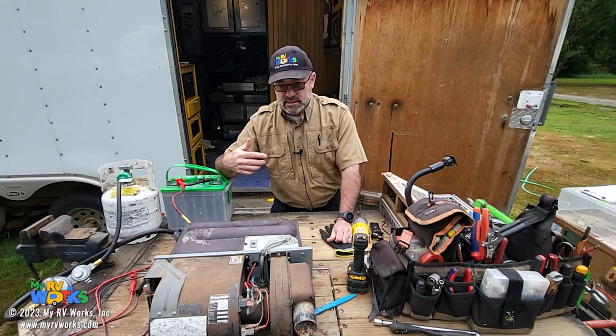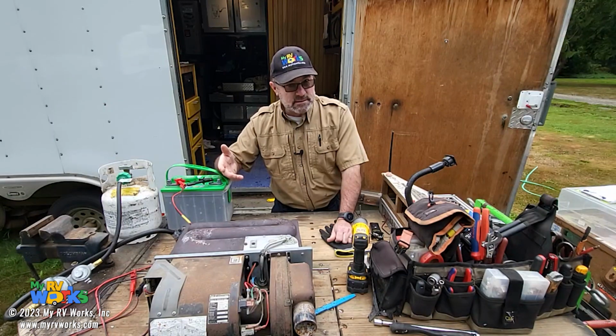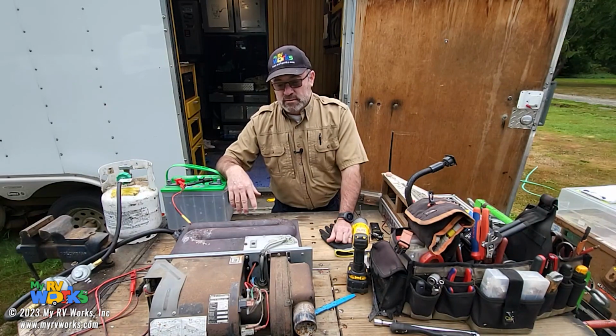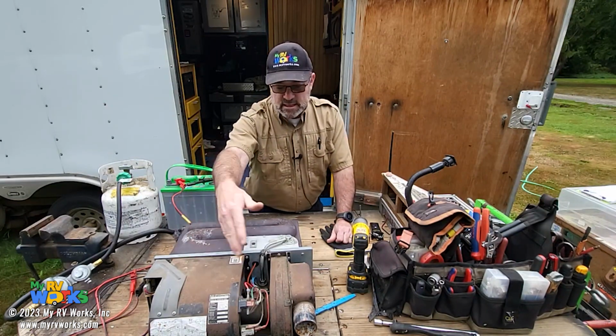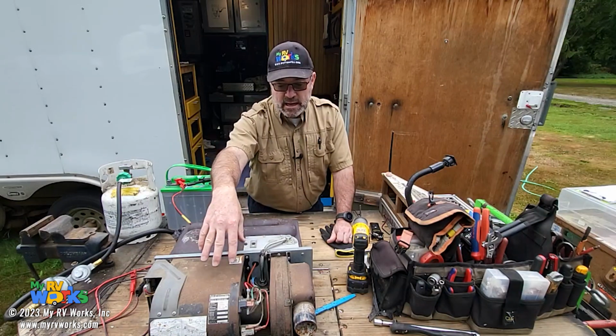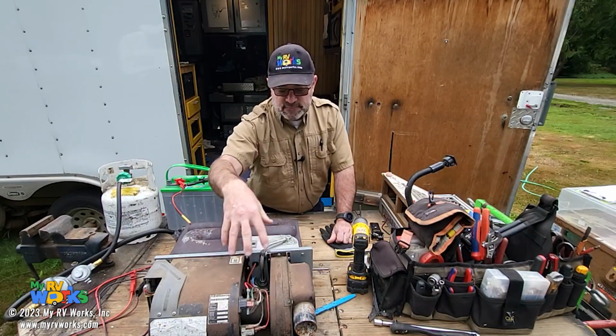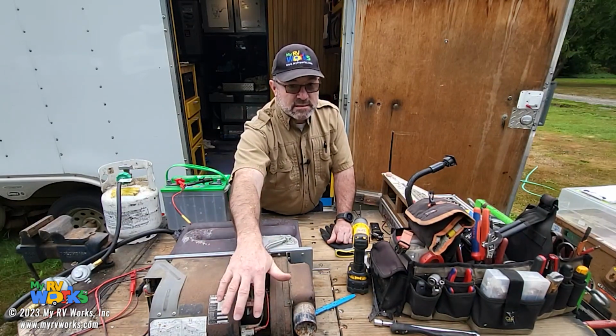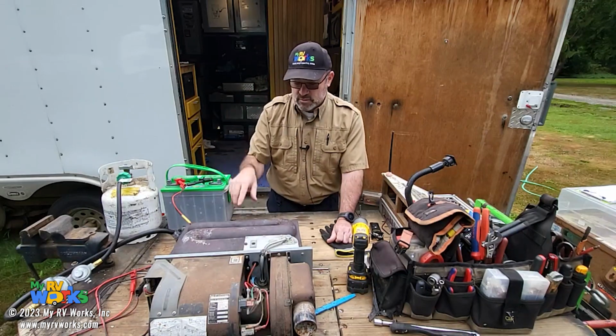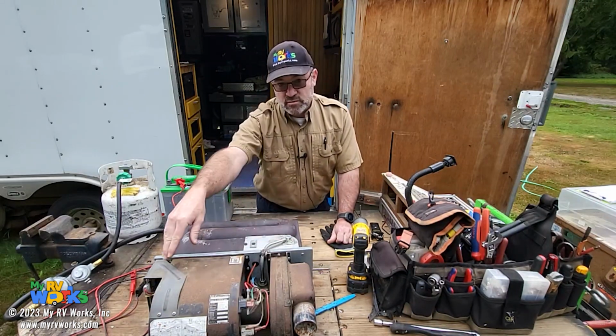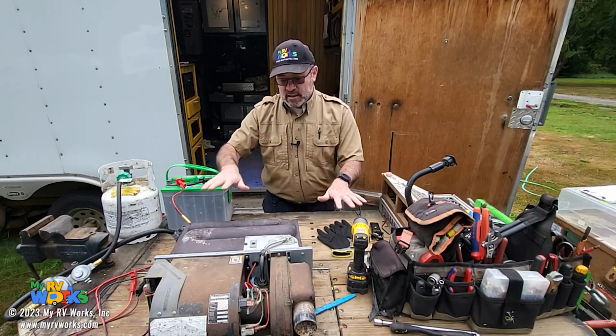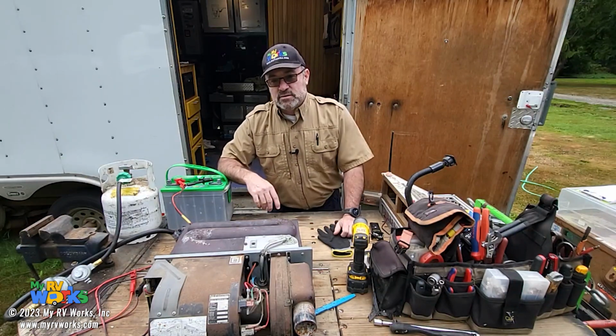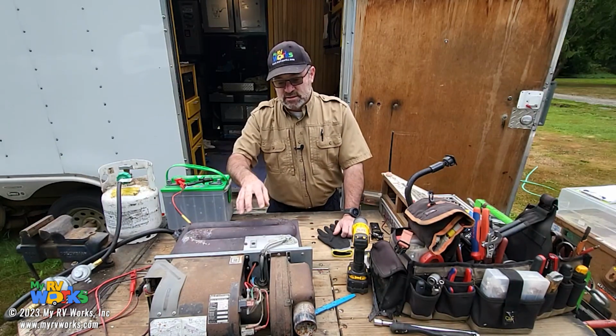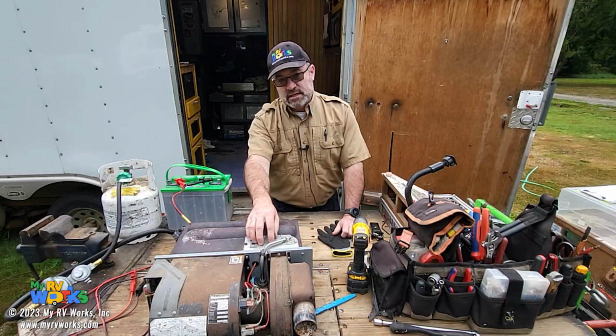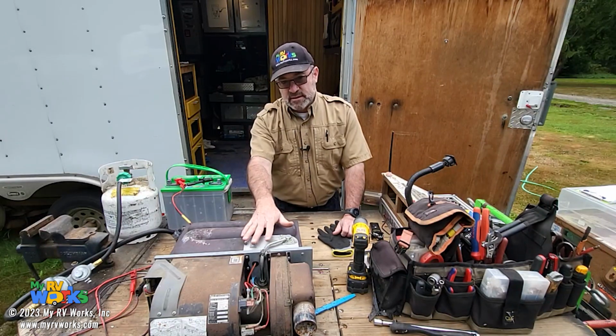It needs to see it start from a zero state, an open state, okay? Not to say that all control boards are the same, because these things are a mixed bag, but typically when we see the fault this one's having, it's typically not a sail switch problem. It's either the high temperature switch, the electrode wire, or the control board. So if your symptom is that your furnace is igniting, extinguishing, igniting, extinguishing, these are some things I'd want you to look at.